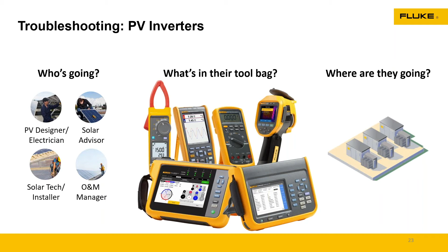In one aspect, I was working with a company and their inverter kept tripping. They determined that the inverter was working correctly, all the components were working correctly. We put a power quality unit on the AC side of the inverter. Come to find out, they were getting dirty voltage coming from the utility. Something downstream was sending harmonics, I don't think it was a transient, but basically, the inverter was smart enough that it caused that to trip out.